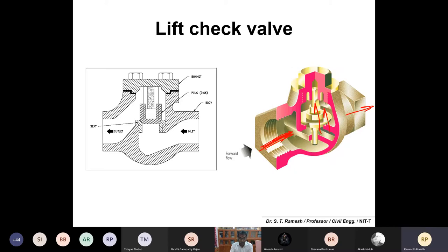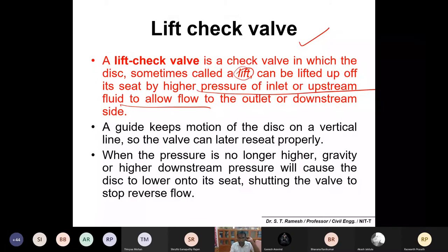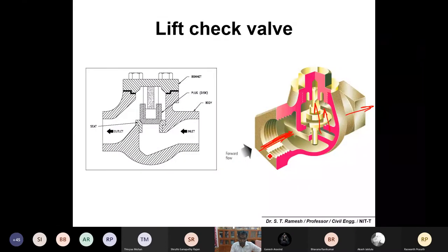The lift check valve is a check valve in which the disc, sometimes called a lift, can be lifted off its seat by high pressure of the inlet or upstream fluid to allow flow to the outlet or downstream side. If sufficient pressure is there upstream, it automatically lifts up and allows water to flow. If sufficient pressure is not there, it will not allow water to flow.